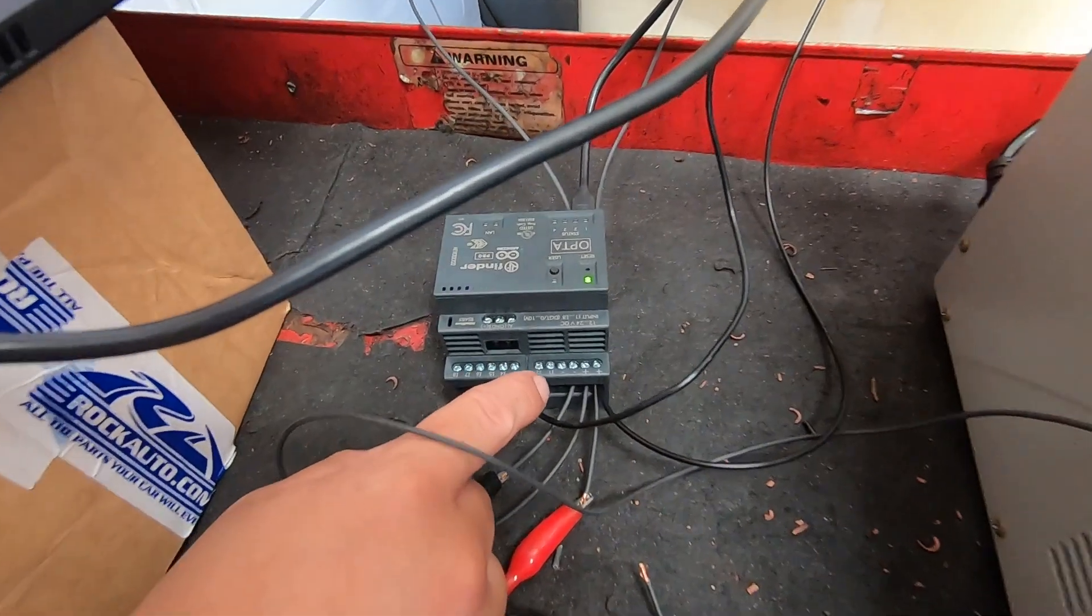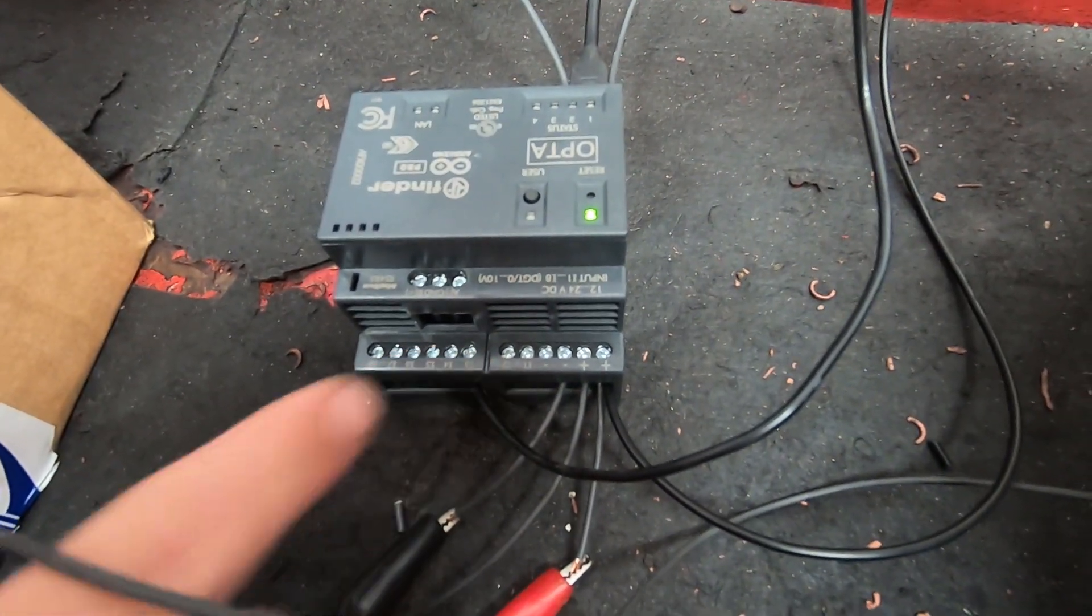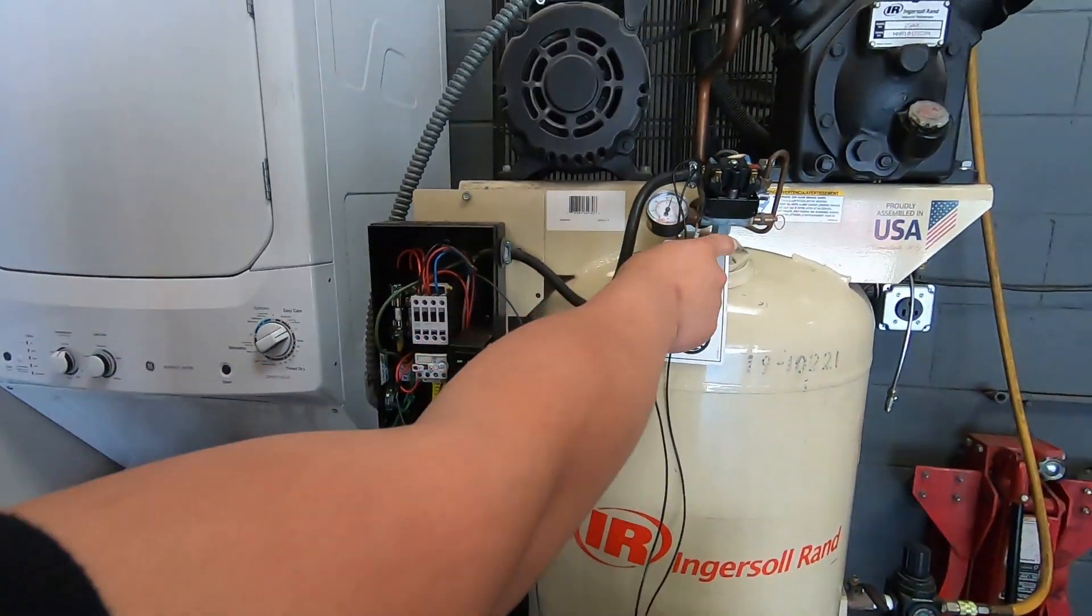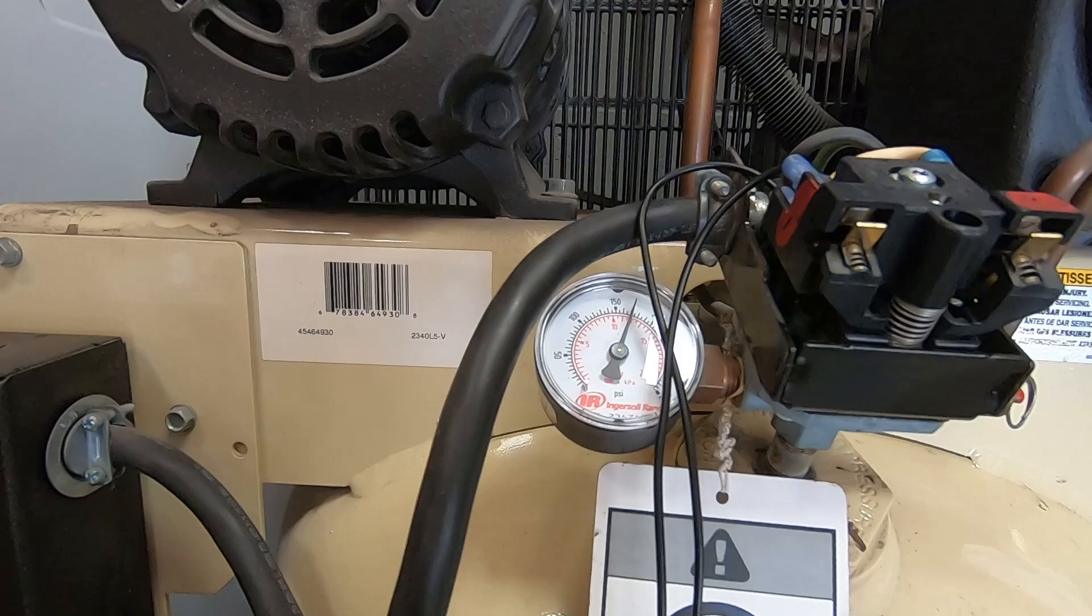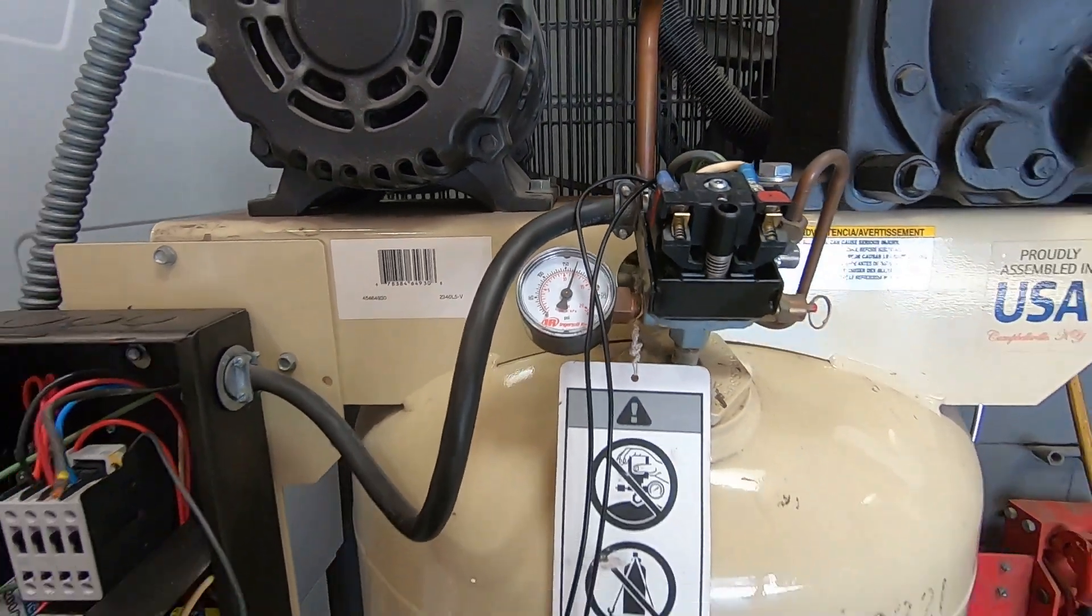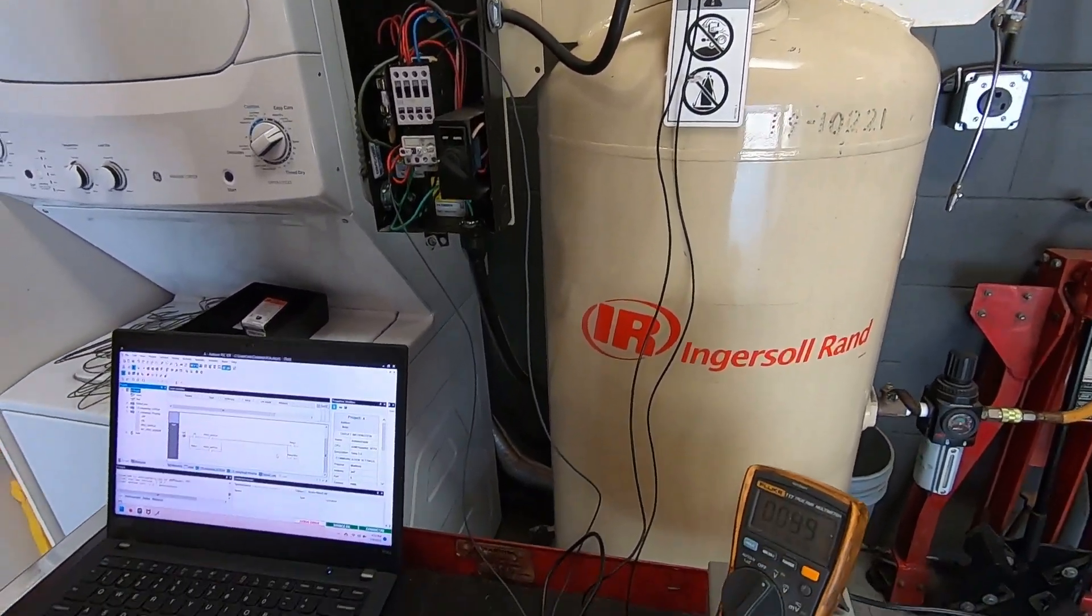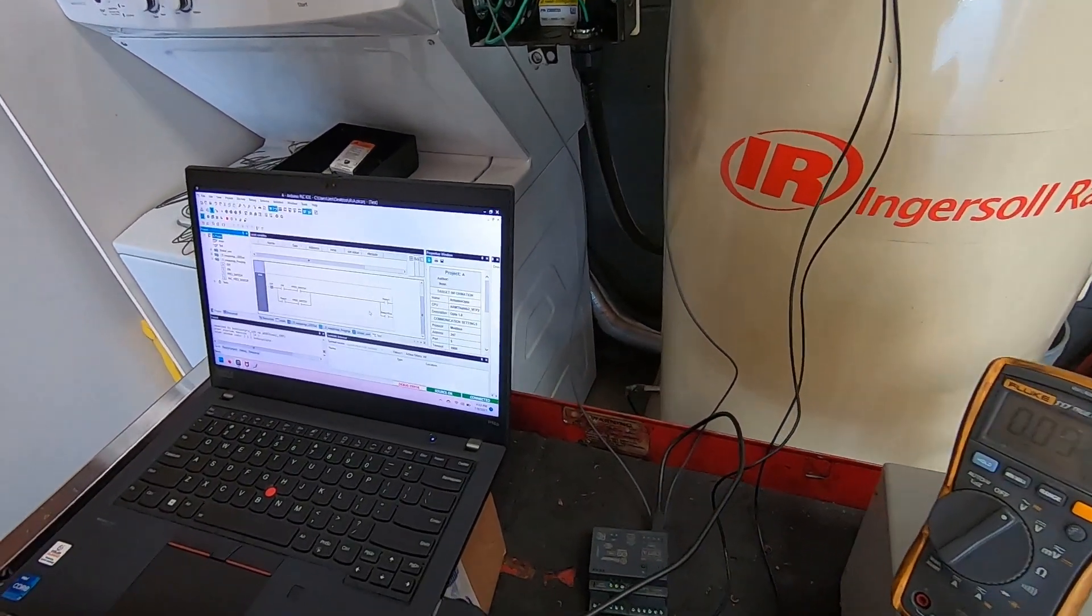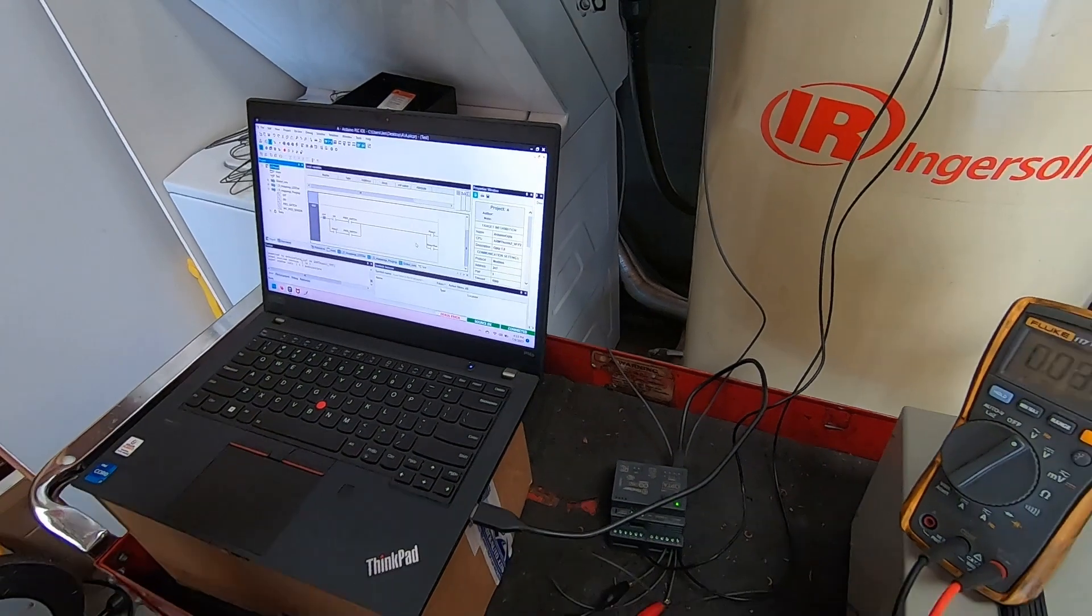It's going to be input one and input two as an on switch and input three is going to be connected to the pressure switch. This is a pressure switch rated at 175 PSI. It'll open the contacts at 175 PSI and then turn it back on at 135 PSI.